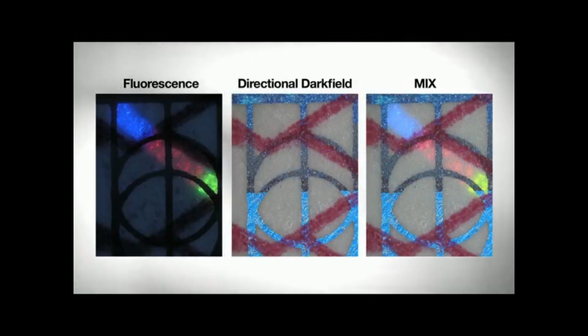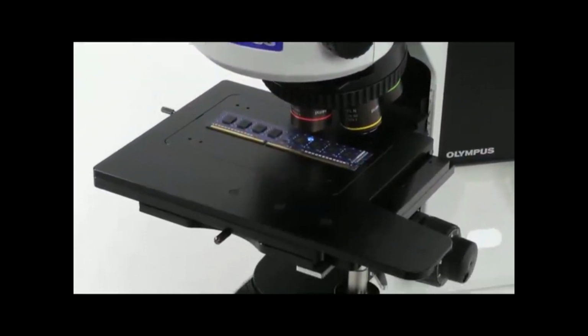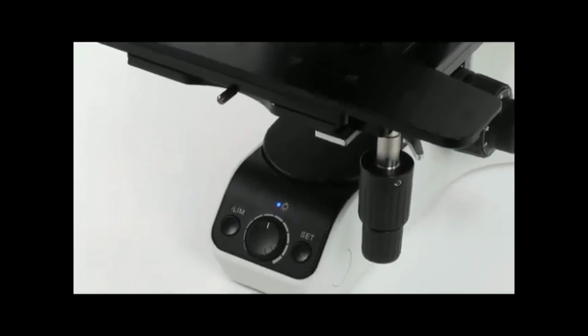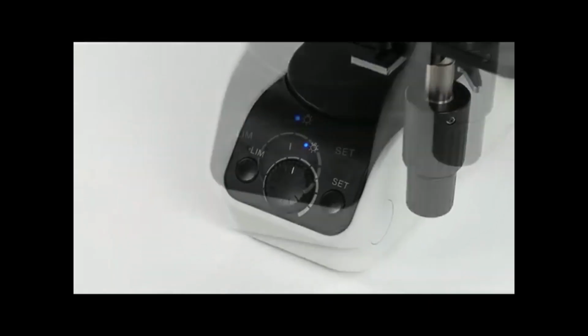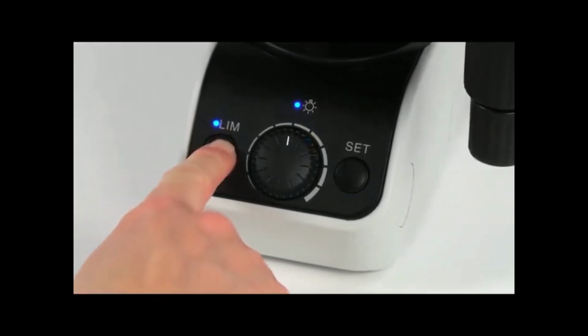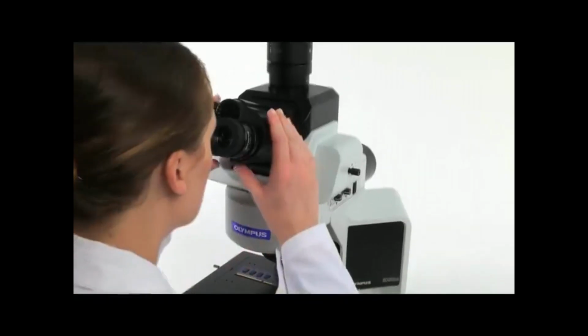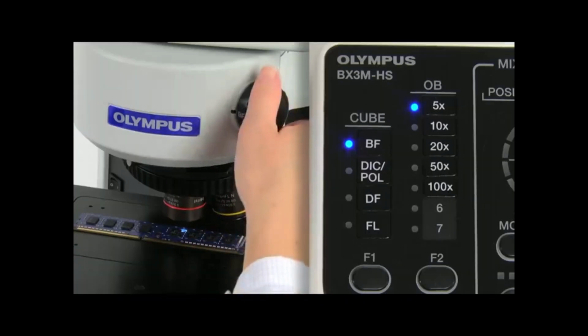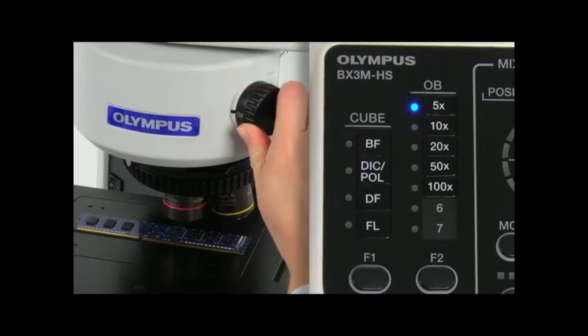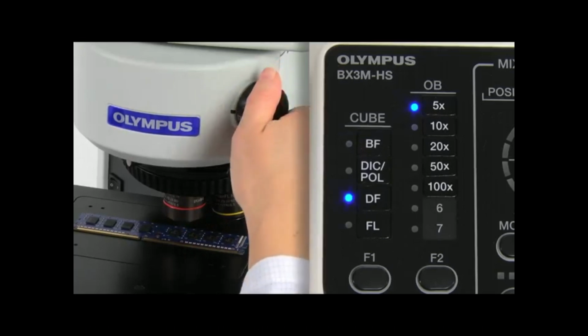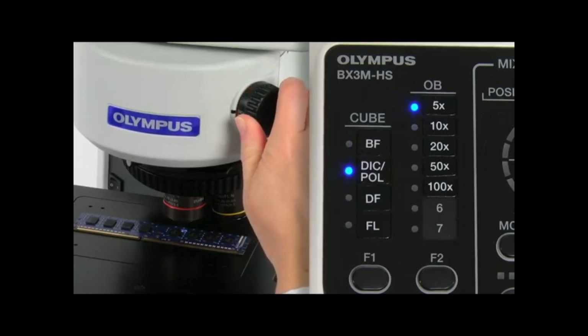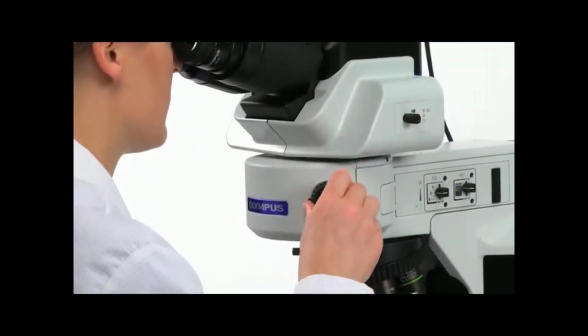single observation method. For traditional observation methods, setting the illumination intensity with Light Manager saves time and minimizes operator training. Light Manager works with coded hardware by adjusting the illumination intensity to preset values when the magnification and observation method are changed. This takes the guesswork out of optimizing the lighting.